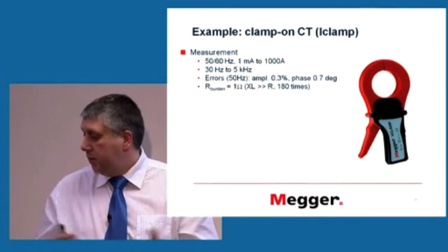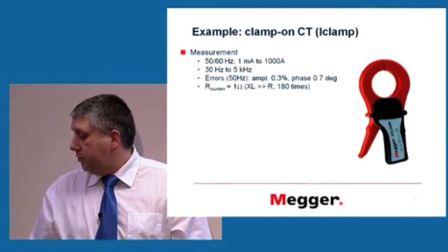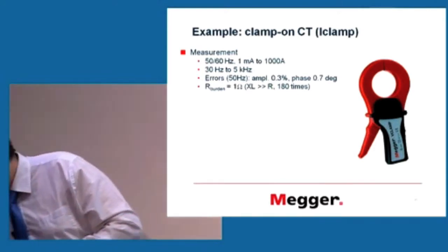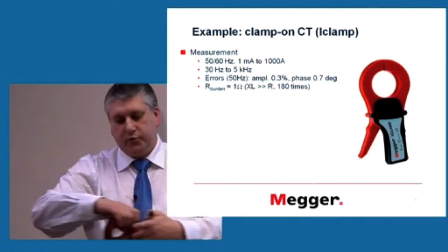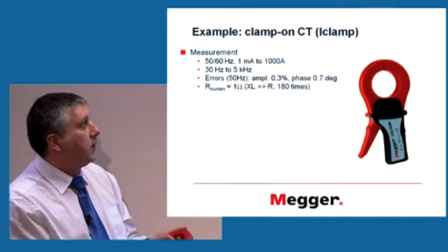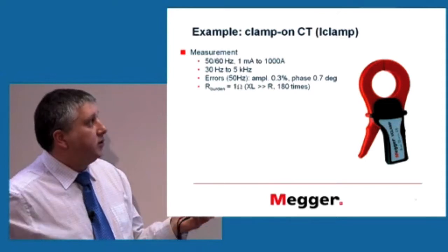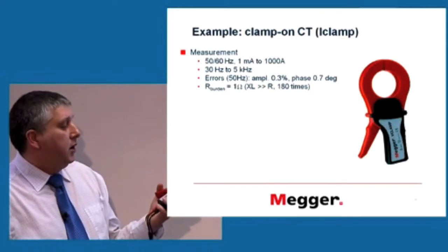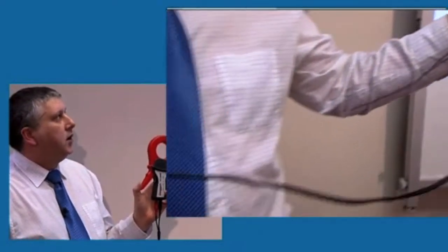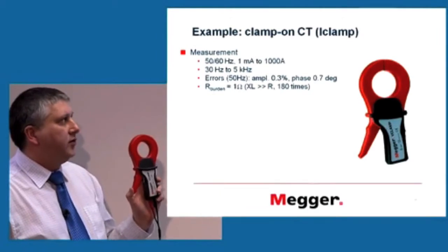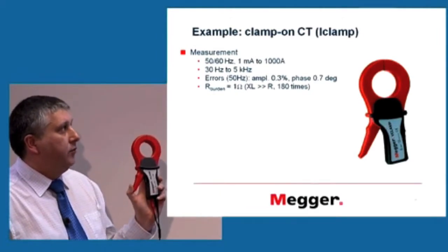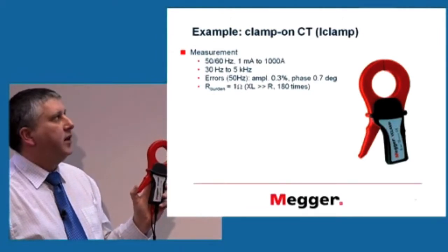Okay, so let's use some examples, which should be quite interesting. This is an example of a current transformer. Its accuracy is guaranteed for 50 and 60 hertz, but it can measure from 30 hertz to about 5 kilohertz. The measurement ranges from 1 milliamp to 1,000 amps.